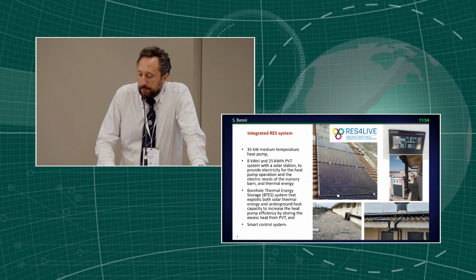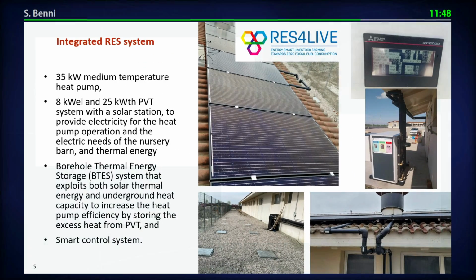So we combined a system with a dual source heat pump, medium temperature, 35 kilowatt, and a solar photovoltaic thermal system with an electrical power of 8 kilowatt and thermal power of 25 kilowatt, controlled by a solar station, and a borehole thermal energy storage, which is in charge of accumulating the excessive heat from the solar panels and storing it underground.